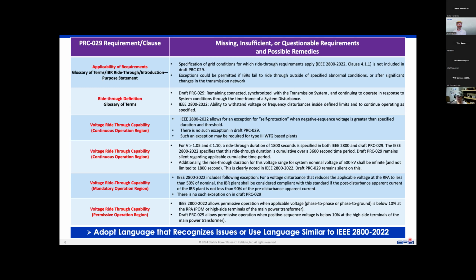NERC PRC 29 in its latest draft currently does not include such limitations. The ride-through definitions seem to be different between the NERC PRC 29 draft and the published IEEE standard. When it comes to voltage ride-through capability, 2800 allows for an exception for self-protection when negative sequence voltage is greater than a specified duration and threshold, whereas PRC 29 does not allow for that exception. Also in the ride-through capability continuous operation region, 2800 specifies certain requirements as cumulative, whereas PRC 29 remains silent on those details.